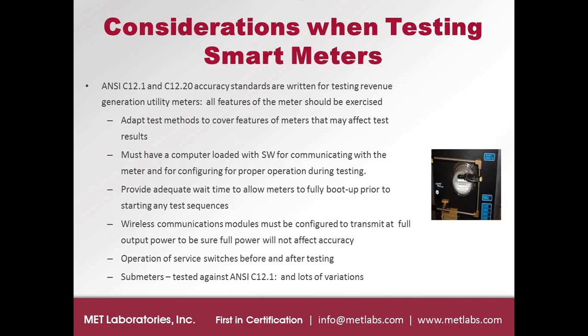We are making sure that we have the proper communications programs. We're always asking that the customer supply us with support equipment. Typically that's a laptop loaded with software so that we can communicate with the meter. It's not just about plugging the meter into our meter accuracy test boards and reading the register off the display. It's also communicating with the product to make sure that's functioning well, and that the software registers are tracking with the meter as well.